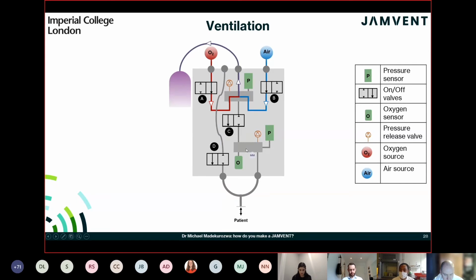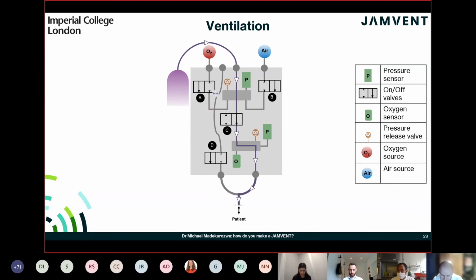After exhalation occurs, a breath is prepared for the patient to breathe in. So the air and oxygen lines open, so valve A and valve B open, allowing air and oxygen to flow into the reservoir. Once enough air and oxygen have flown into the reservoir to deliver one breath to the patient, the air and oxygen lines close, as shown in this figure over here.